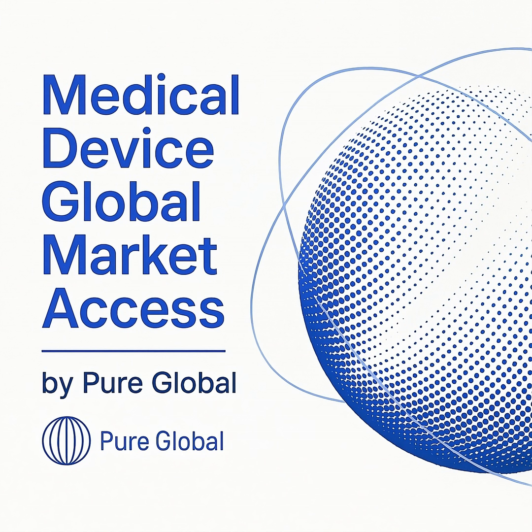The central pillar of a 510K submission is demonstrating substantial equivalence to a legally marketed device in the US, known as a predicate device. This is a fundamental difference from the European approach, which focuses on demonstrating conformity to general safety and performance requirements. Your first step is to identify a suitable predicate and prepare a detailed comparison of your device's intended use and technological characteristics against it.